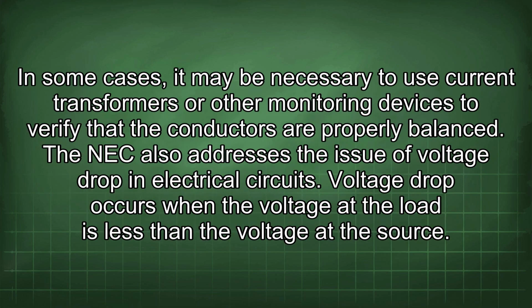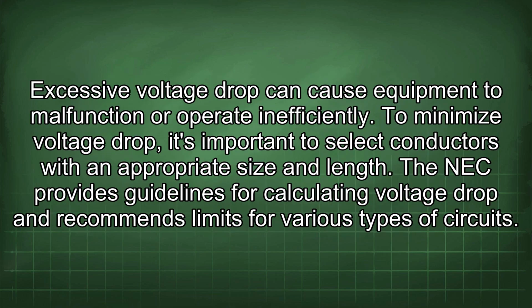In some cases, it may be necessary to use current transformers or other monitoring devices to verify that the conductors are properly balanced. The NEC also addresses the issue of voltage drop in electrical circuits. Voltage drop occurs when the voltage at the load is less than the voltage at the source. Excessive voltage drop can cause equipment to malfunction or operate inefficiently. To minimize voltage drop, it's important to select conductors with an appropriate size and length. The NEC provides guidelines for calculating voltage drop and recommends limits for various types of circuits.